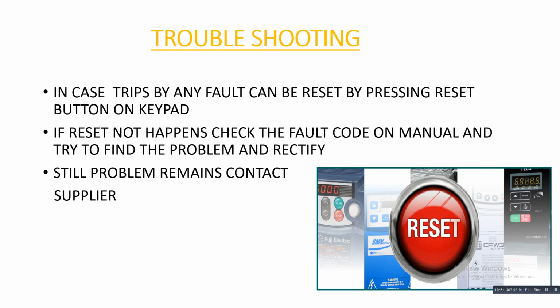In case it trips, you can simply reset it by pressing the reset button on the VFD. If after pressing it does not reset, you have to check why it tripped. Obviously it will show the fault code on the display, so you have to refer to the manual for each fault. Whatever fault code it is showing, the rectification must be mentioned, so you have to follow it as it is. If the problem still remains the same and you are not able to solve the issue, then you can contact the supplier, or if it is fully damaged, you have to replace it.